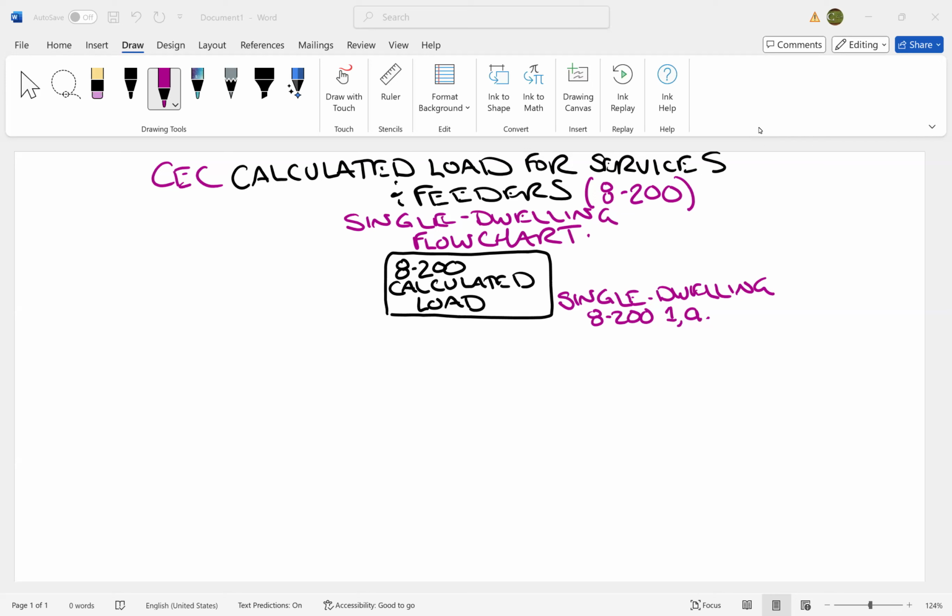The first one is the floor space. A larger home is assumed to use more power. The next one is your comfort conditioning. By comfort conditioning, I mean cooling loads and heating loads, but you're never cooling and heating at the same time, so it is just the largest of the cooling or heating loads. Then it is an electric range, because that's a pretty big element to consider.